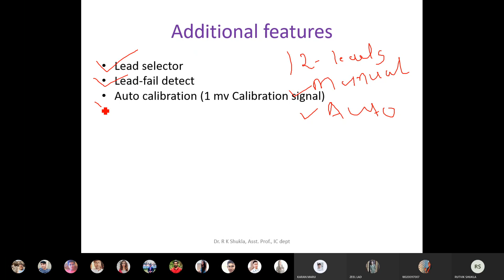So whenever we talk about calibration in instrumentation, we say that calibration is necessary to check whether the instrument is working in proper condition or not. For that calibration, sometimes it is performed on a yearly basis, sometimes on a monthly basis, sometimes on a weekly basis, or sometimes on a daily basis. But here the calibration is performed for each particular reading. So suppose in a day the machine is used 30 times, or for taking the ECG of 30 patients, then during each and every reading, the machine itself calibrates by providing a 1 millivolt standard calibration pulse.